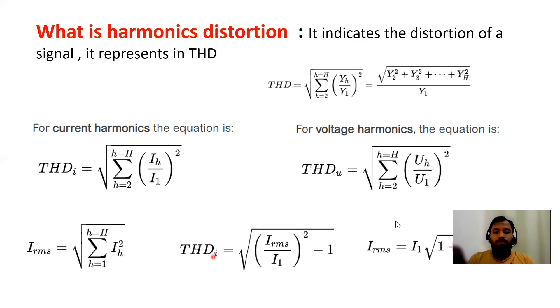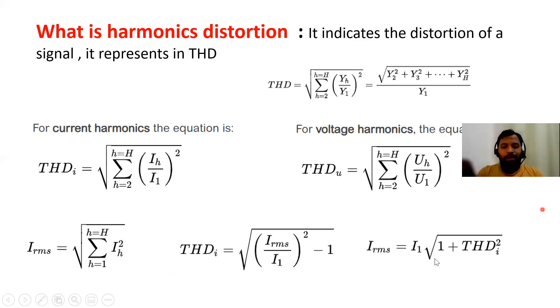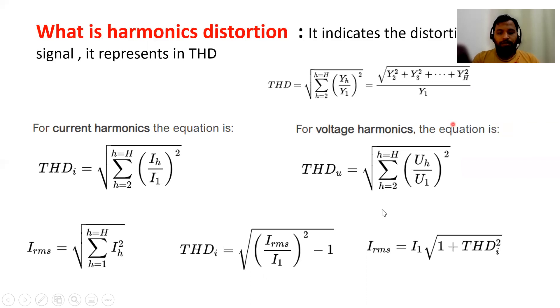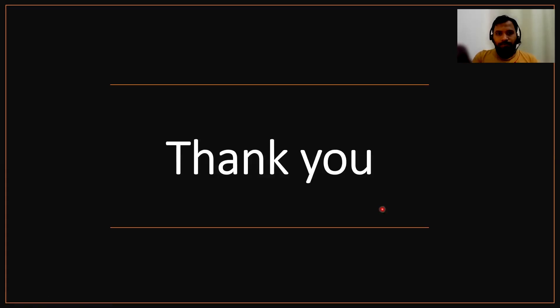The RMS current formula is: I_rms = I1 × √(1 + THD²). And the THD in terms of current is: THD_I = √((I_rms / I1)² − 1). These formulas help find the harmonic distortion. Thanks for watching. In the next video, the effects of harmonics will be explained. Stay tuned — good day!